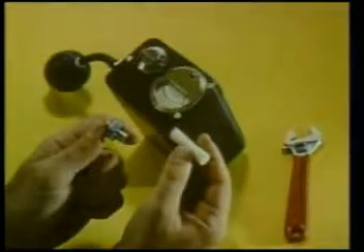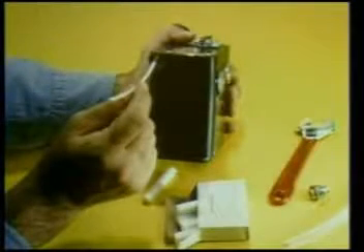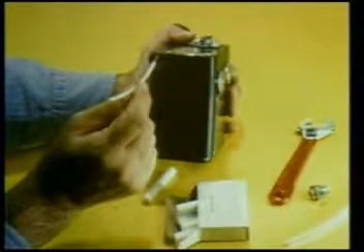The instrument has a replaceable cotton filter to remove smoke, dust, or moisture from the sample. The filter should be replaced regularly. If the filter gets wet, it should be replaced immediately. The explosimeter indicator must never be used without a filter. The filter is replaced by unscrewing the sample inlet coupling. Remove the filter and clean the chamber with a pipe cleaner or dry cloth and install a new filter.